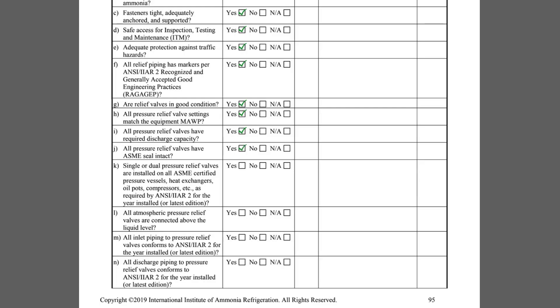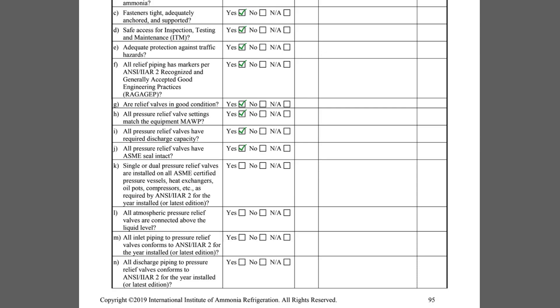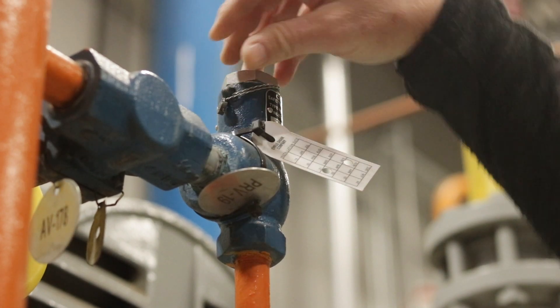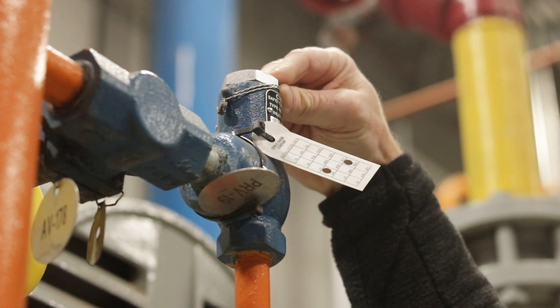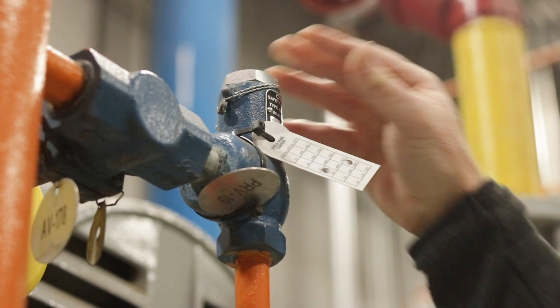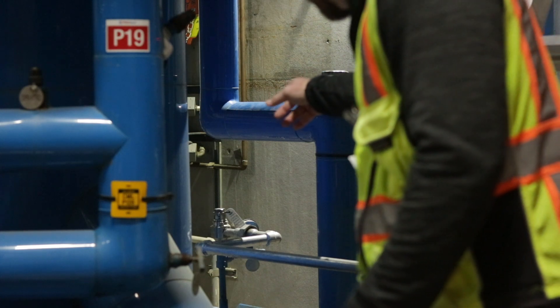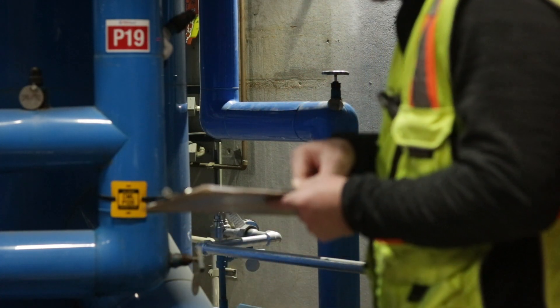Item J asks if all the relief valve seals are intact. The relief valves are sealed by the manufacturer. A broken seal is an indication that the relief valve has been tampered with, which would require valve replacement.